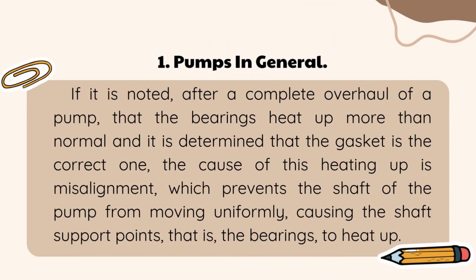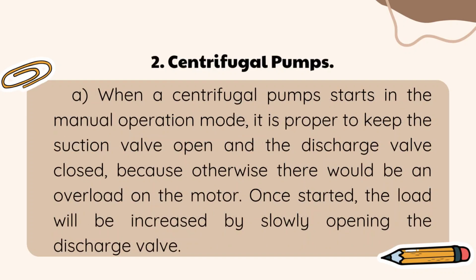1. Pumps in general. If it is noted, after a complete overhaul of a pump, that the bearings heat up more than normal and it is determined that the gasket is the correct one, the cause of this heating up is misalignment, which prevents the shaft of the pump from moving uniformly, causing the shaft support points, that is, the bearings, to heat up.